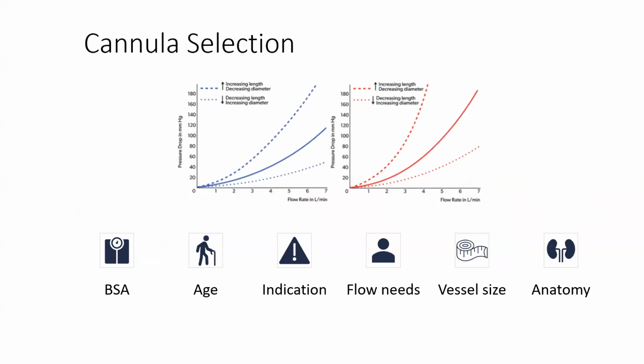Cannula selection, it really depends on what we are using ECMO for. Are we using it for respiratory, or are we using it for cardiac reasons? Are we cannulating peripherally, in the neck, or centrally? What's your patient size? How old are they? What are your flow needs? Vessel size, anatomy. The same laws of physics, like Poiseuille's law for resistance, are the reason how we pick cannulas. A cannula that is longer with smaller diameter, and thus higher resistance, is going to tolerate lower flow rates and have more of a pressure drop. We use these types of charts up at the top to help us choose the appropriate cannula based off of the flow that we'd like to give to our patients.